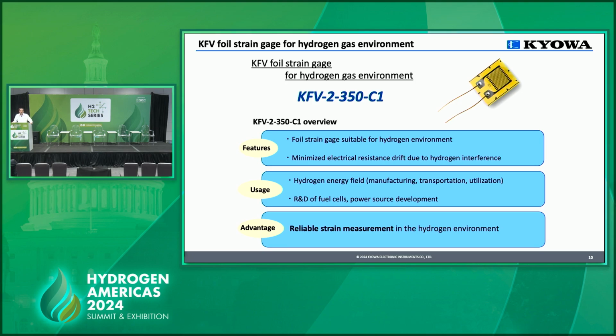Kyowa Electronic Instruments in Japan has developed a unique solution for hydrogen environments. This is the KFV model, a strain gauge for hydrogen gas environments. Kyowa's engineering team uses a special material, iron chromium alloy, for the sensing portion of the strain gauge, so we can minimize electrical resistance drift due to hydrogen embrittlement.